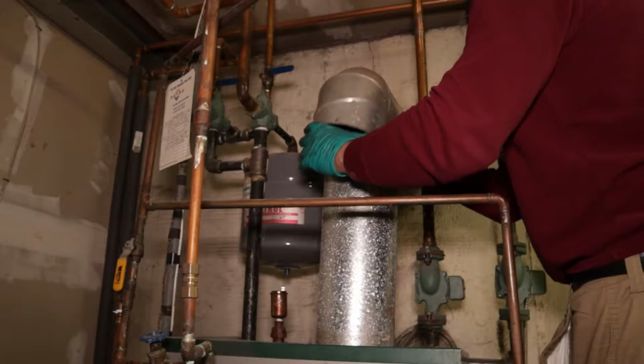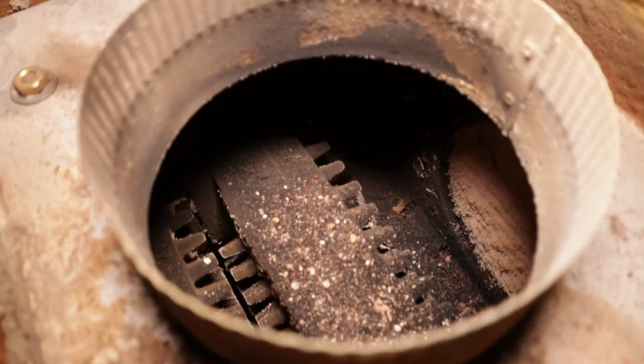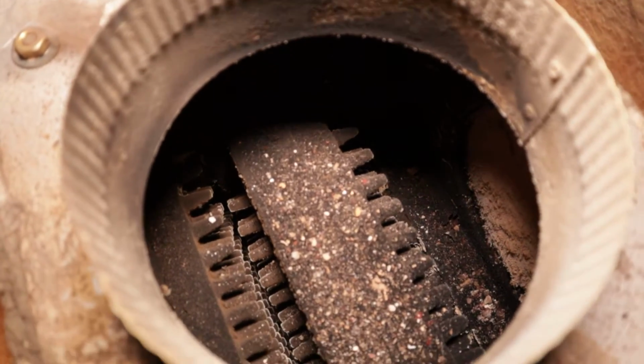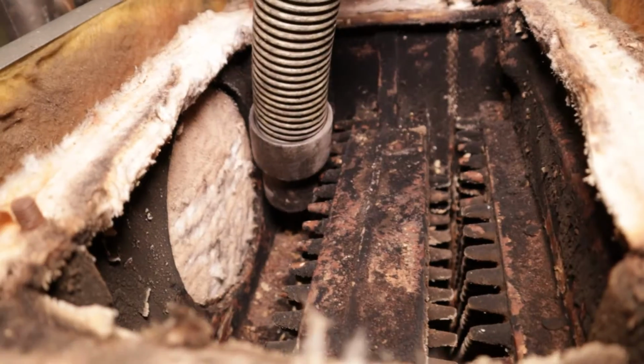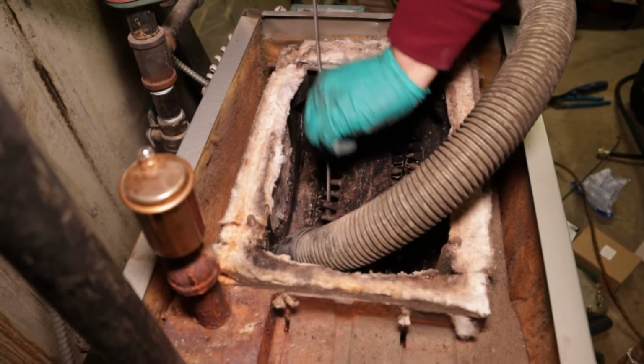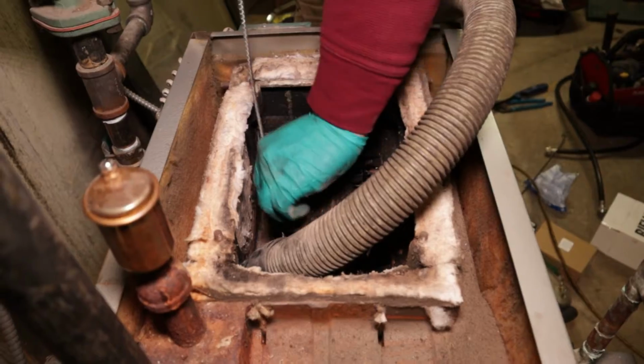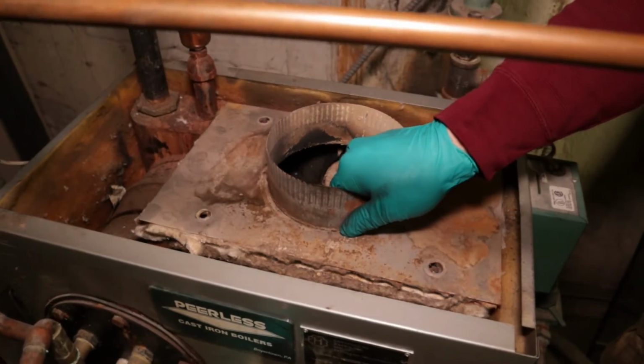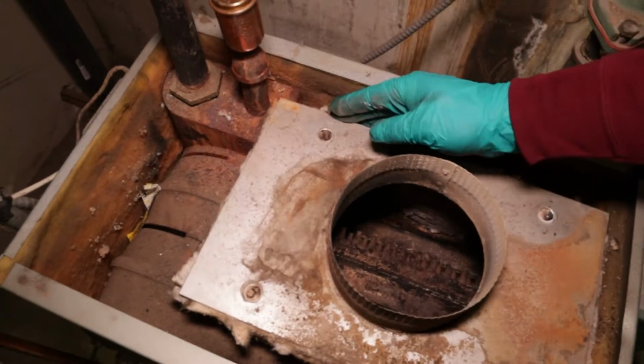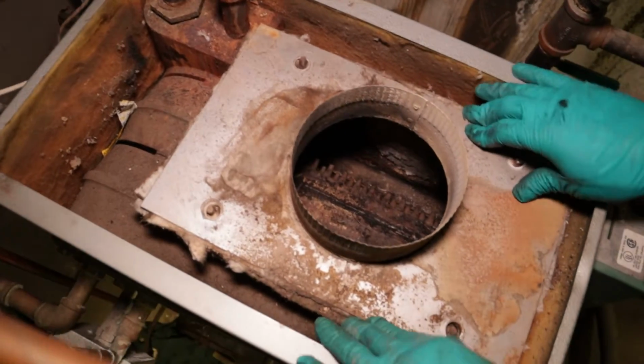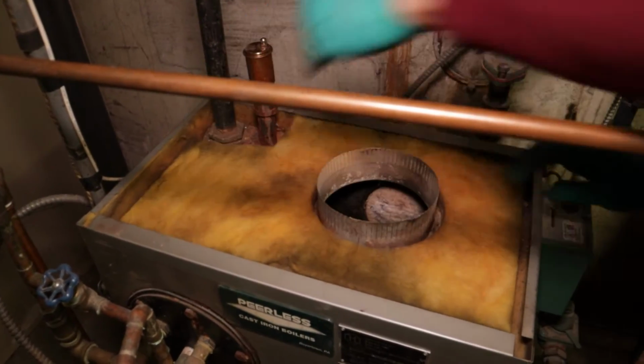Next thing is we're actually cleaning out a heat exchanger of the oil boiler. Take out the cover, remove the cover, get access to the heat exchanger and place the vacuum hose inside the heat exchanger, and you guys start brushing down the heat exchanger. Once you guys are done, put everything back together. Put the cover back on, put the main cover back on, and now we're gonna start working on putting the flue pipe back together.